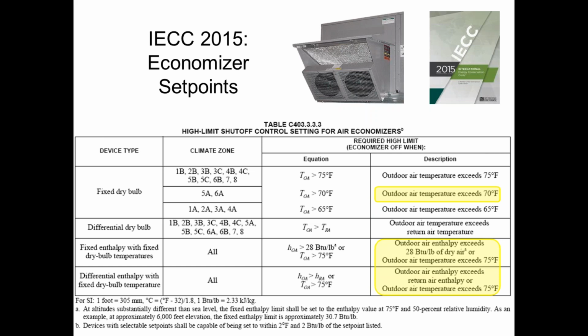Some of the controllers, like the very popular Jade controller that is used on most manufacturers' rooftops nowadays, does not have an exact setting for 28. I think 26 lines up with a 75 degree point, and 28 lines up with like 80 degrees. So you're setting it for 26 and 75. And there's been some argument that that doesn't really comply with the code. But it actually does comply with the code. If you look at note B down at the bottom that I'm highlighting, devices with selectable set points will be within 2 degrees and 2 BTUs of the set point listed. So I can make this 26 to 30 BTUs, and I can make this 73 to 77 degrees if I need to be more adjustable to find a product that works. But essentially, I'm in that ballpark of 28 and 75.